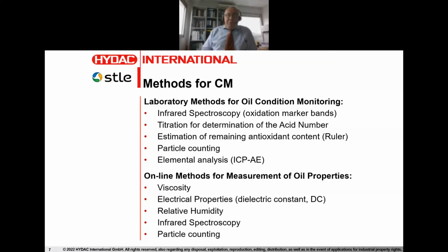One can also include ultraviolet-visible spectroscopy for analysis of color. Typically the oils tend to shift to the red, meaning they tend to acquire yellowishness and brownishness as they age. So we can see a shift in the ultraviolet-visible absorption spectrum to the red. It's not typically used, so people typically fall back to something simpler like the ASTM color analysis, which is simply visual assessment, but that tends to be a little bit subjective because not all of our eyes read the same way. Whether it's a color number 5 or color number 3 is sometimes difficult to say. And since a lot of these methods were carried out at industrial facilities, not every power plant or steel mill wanted to invest in instruments for all this rather more sophisticated approach.